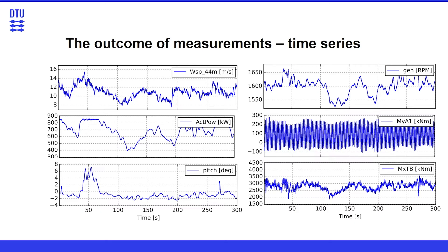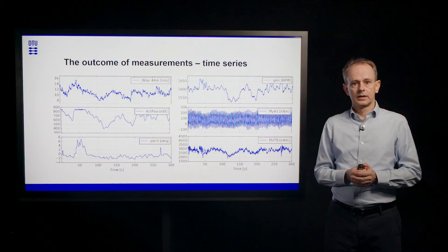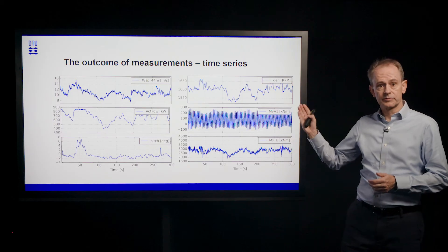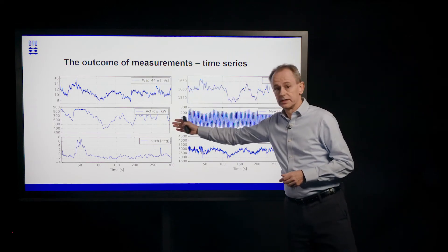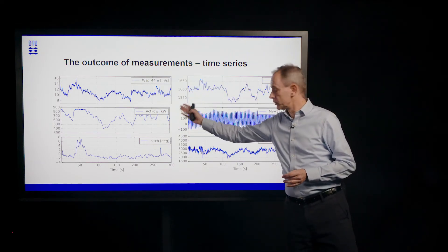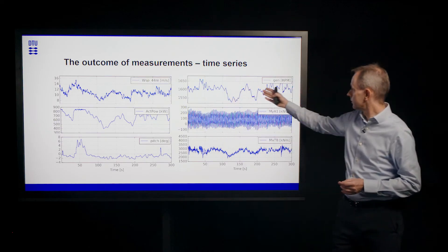The outcome of the measurements is time series. Typically, it's 10-minute time series with a sampling frequency of 20 to 50 hertz. And by using that sample frequency, we can resolve the dynamics of a modern large turbine. Here we see a few examples of measured time series. We see the wind speed, we see the power production of the turbine, we see the pitch angle and the generator speed.